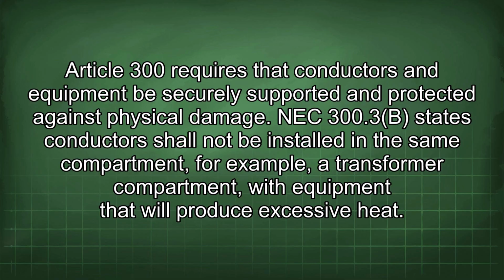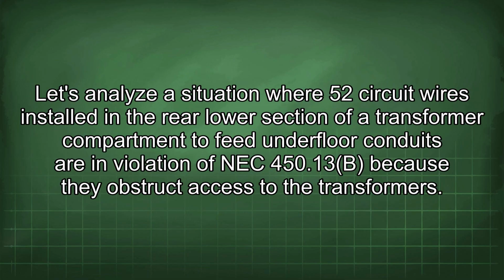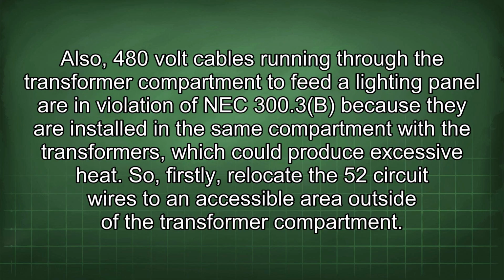will produce excessive heat. Let's analyze a situation where 52 circuit wires installed in the rear lower section of a transformer compartment to feed underfloor conduits are in violation of NEC 450.13b because they obstruct access to the transformers. Also, 480-volt cables running through the transformer compartment to feed a lighting panel are in violation of NEC 300.3b because they are installed in the same compartment with transformers, which could produce excessive heat.